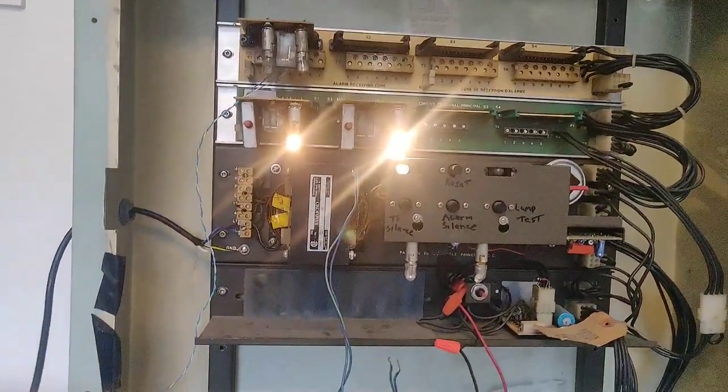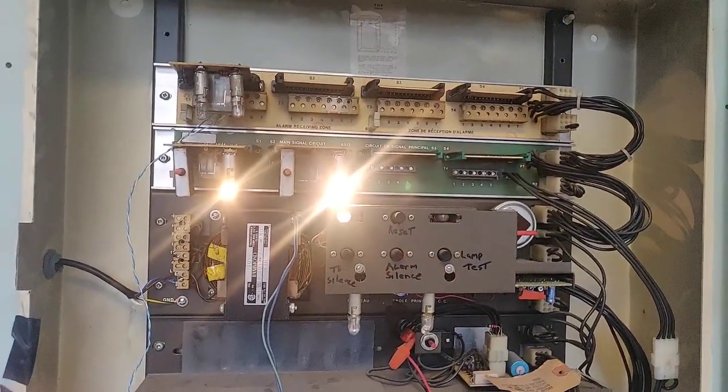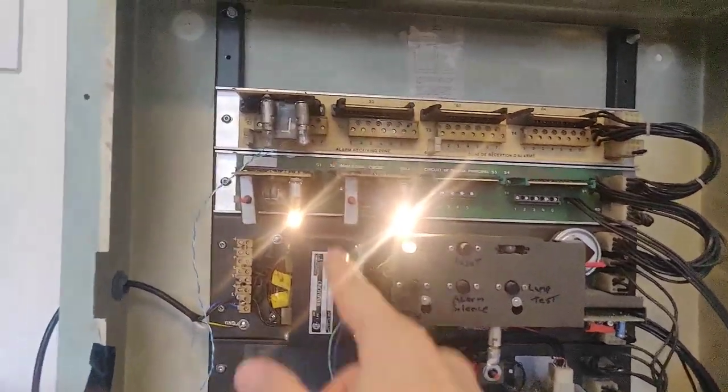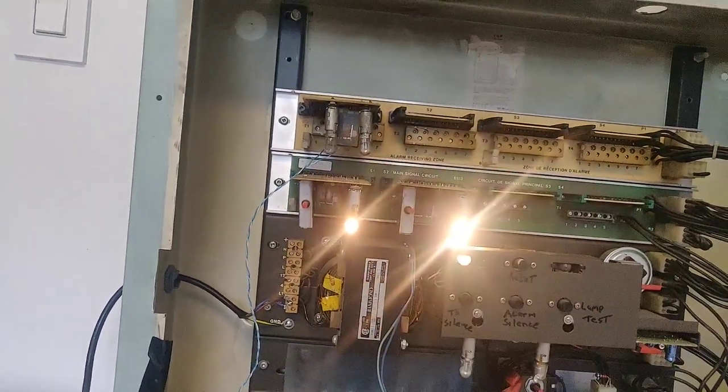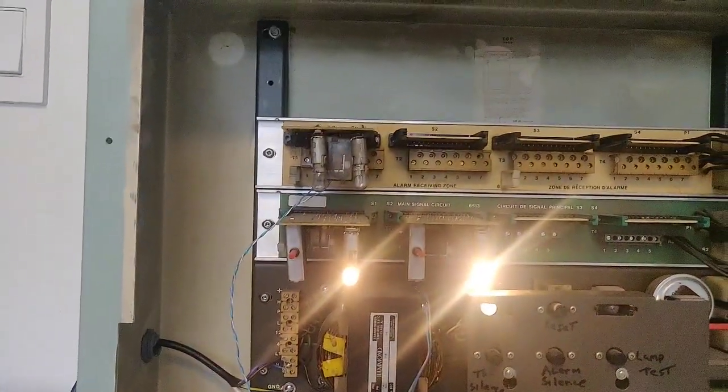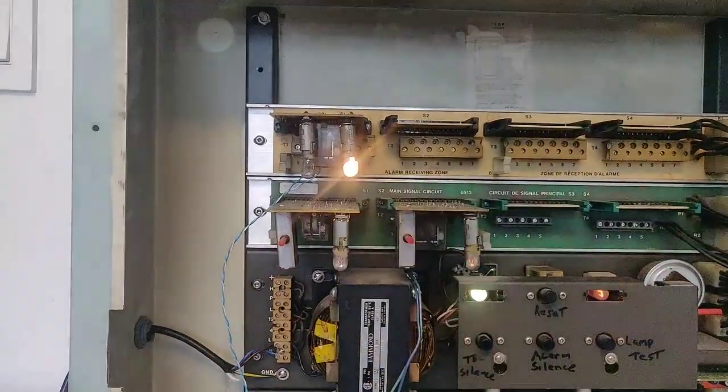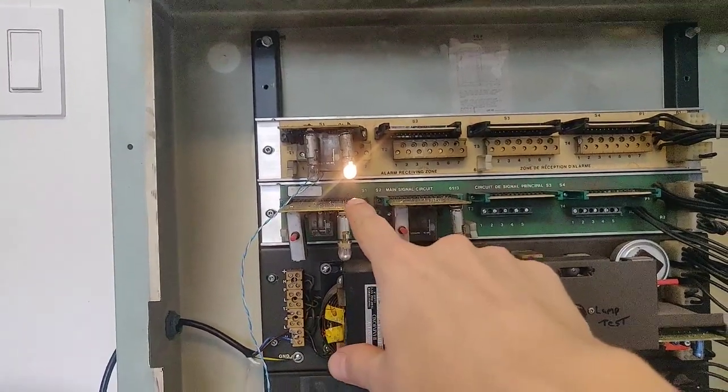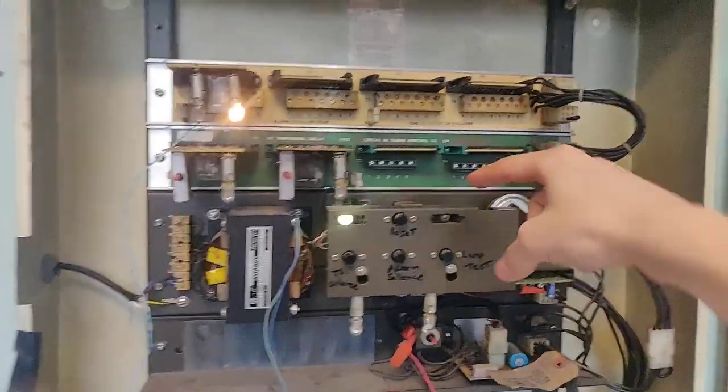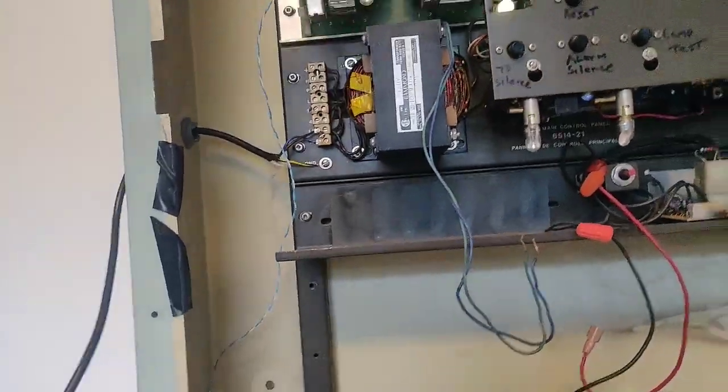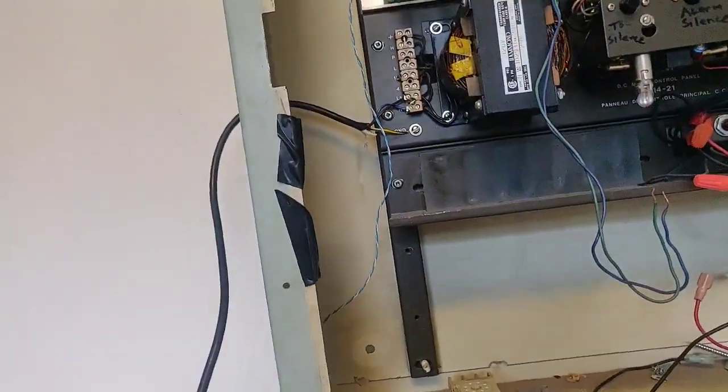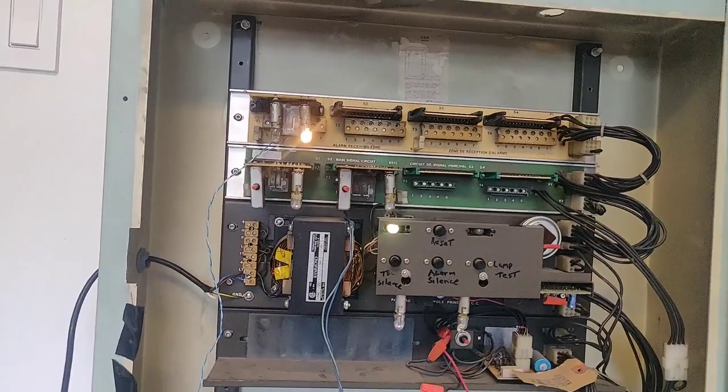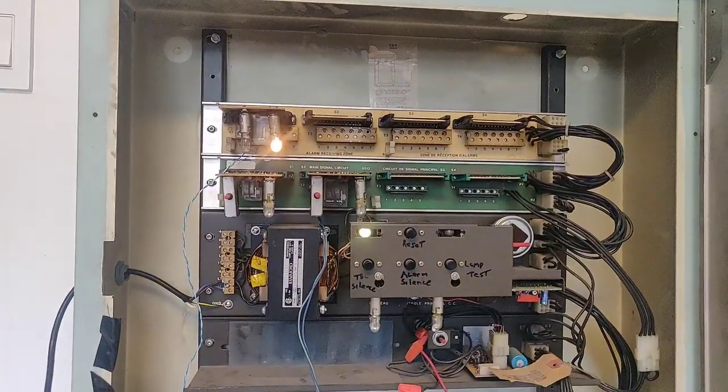So I'm going to silence the trouble warning. So that there means that it's silenced, that blinking. On our initiating circuit card, you can see the trouble light is not on, it's not illuminated. So let me pull the pull station and we'll see this zone going to alarm. So the light on the right hand side should come on when this is in alarm. There you go. You can see the trouble lights click off and that goes on meaning it's an alarm. So if I hit reset, nothing happens. And that's actually caused by that relay having a bad set of contacts. So what I'm going to do is shut off the power and turn it back on to reset the system. So the power has been turned off to the panel. And there we go. I have made a critical error which is that I left the pull station pulled. So let me reset it and we will come back in a second.